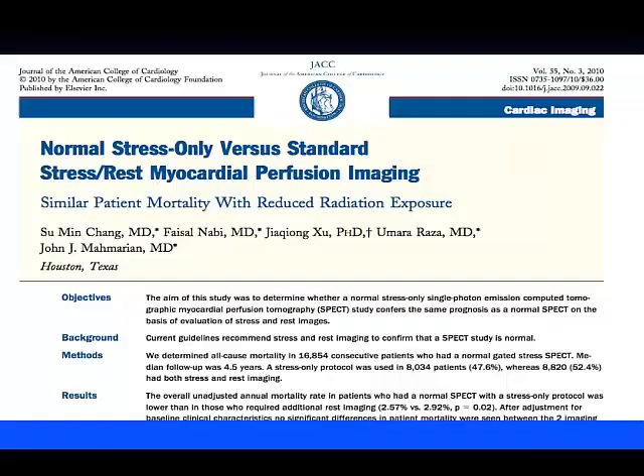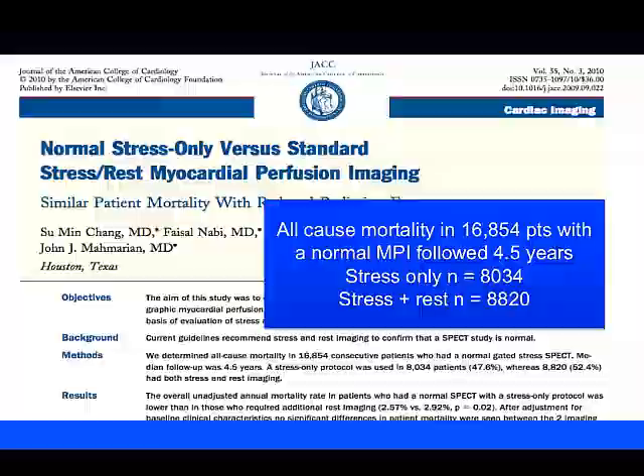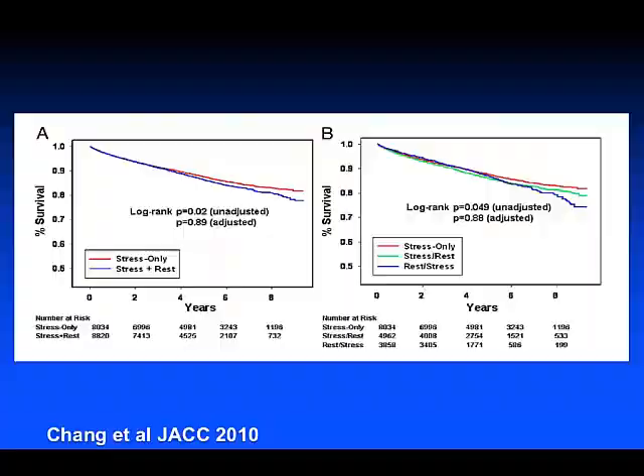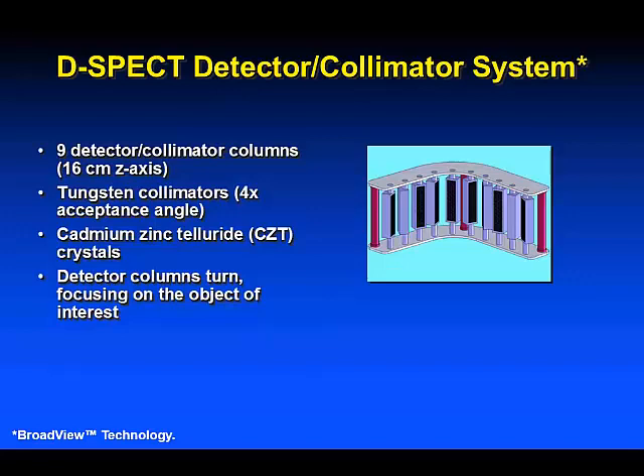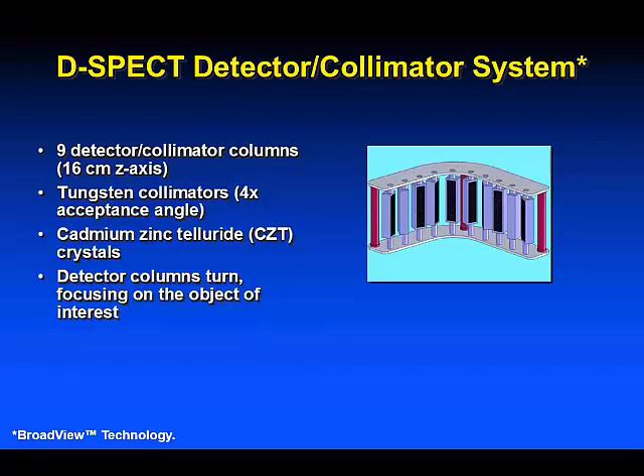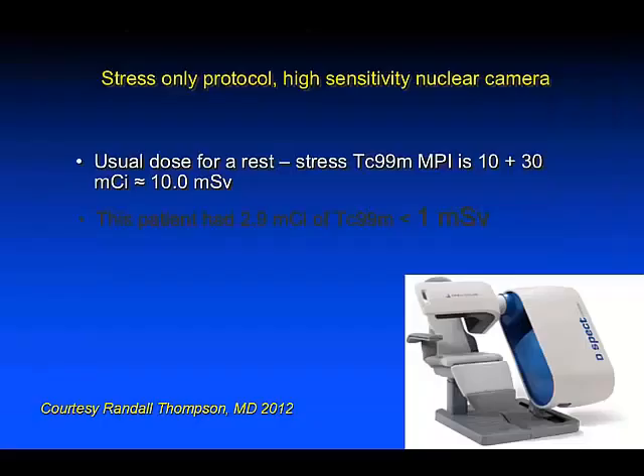Stress-first, stress-only imaging is well validated. Work from the Baylor group and John Mahmarian in 17,000 patients shows excellent outcomes very similar to stress-and-rest imaging, with 61% less radiopharmaceutical use. The Spectrum Dynamics camera we use at Rochester involves nine collimated detectors that rotate, enabling two-minute imaging at low dose with iterative reconstruction — 10 times the speed of acquisition, 2 times the spatial resolution, and lower radiation dosage. A high-quality stress-first study used only 2.9 millicuries of Tc-99M — less than 1 millisievert — to achieve a diagnostic normal study.